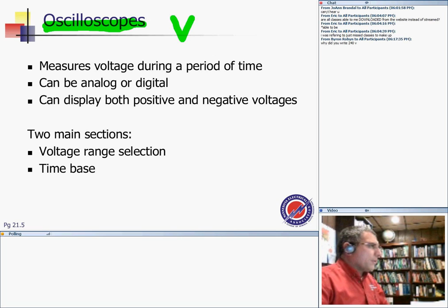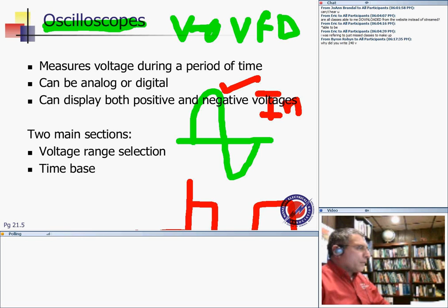Suppose you have a VFD, a variable frequency drive. The input of the VFD is a nice sinusoidal wave coming in, and the output of the VFD is a step voltage to control the speed, so your voltage looks like a step voltage. An oscilloscope can draw this for you, measuring the voltage and showing the voltage range - you'll see a signal that looks like steps. That's how the input should be, and my output for this device should look like a step voltage coming to the motor. If it's not looking like this, it means there's something wrong in the DC rectification of the signal.